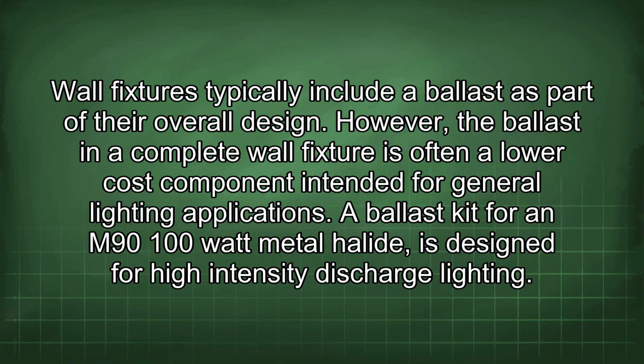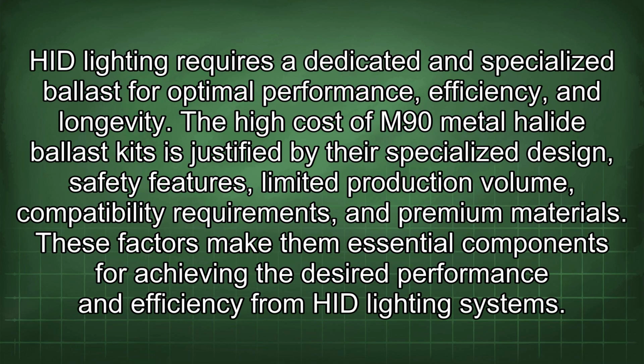Wall fixtures typically include a ballast as part of their overall design. However, the ballast in a complete wall fixture is often a low-cost component intended for general lighting applications. A ballast kit for an M90 100-watt metal halide is designed for high-intensity discharge lighting. HID lighting requires a dedicated and specialized ballast for optimal performance, efficiency, and longevity. The high cost of M90 Metal Halide ballast kits is justified by their specialized design, safety features, limited production volume, compatibility requirements, and premium materials. These factors make them essential components for achieving the desired performance and efficiency from HID lighting systems.